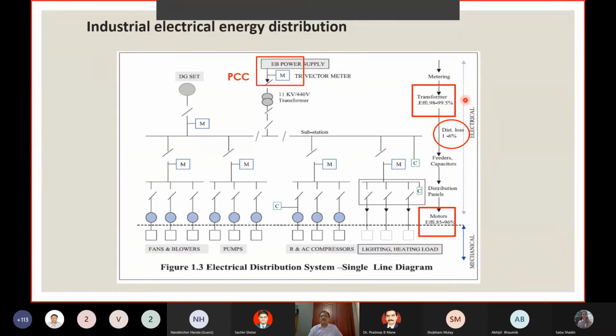So this is the installed load, and this is the end-use load. As you can see on the right-hand side, I have circled the losses as they exist, as found by TERI, the Energy and Resources Institute, which is based in Bangalore and Delhi, a very leading organization so far as energy auditing and energy policies are concerned in our country. Transformer efficiencies are between 98 to 99.5%. Distribution losses are between 1 to 6%. And motor efficiencies are between 85 to 96%. 85% will be for average low rating motors, which we call small motors, and 96% could be for very large motors, like 160 kilowatt, 200 kilowatt, and so on.